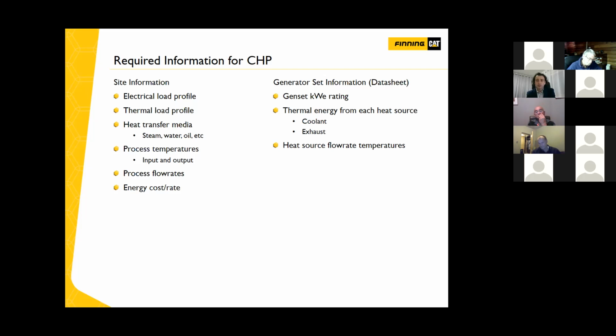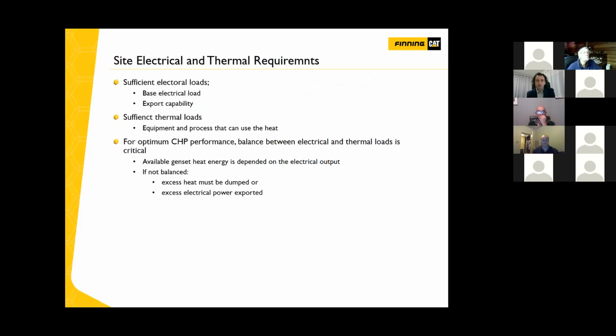From the generator set data sheet, we can obtain genset kilowatt ratings stating the electrical output, thermal energy from each heat source—coolant and exhaust—heat source flow rates, temperatures, and so on. This is some of the basic information needed to select the genset and choose the appropriate heat source. Additional information will probably be needed from the site to properly do a complete feasibility study. There's obviously a lot more to it than we'll have a chance to show here tonight.